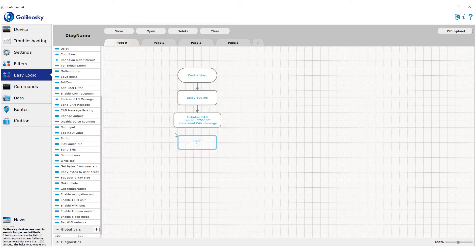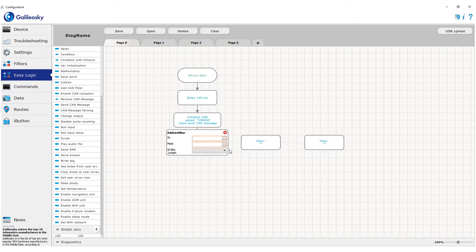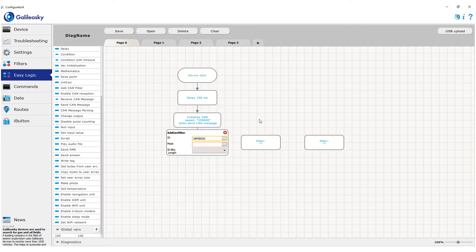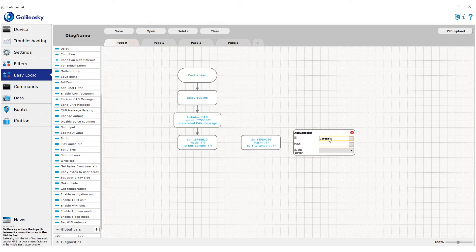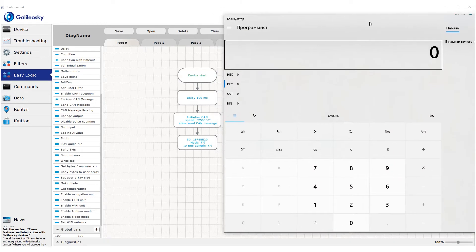Then we start adding CAN filters to the scheme. Filters are needed to work only with the identifiers we need and ignore all the rest. Each identifier uses a separate filter block. In the first field, we enter the ID of the message. As I already said, EasyLogic works with decimal values only, which is why we can remember one of the previous lessons and make the reading of the algorithm more convenient. We can create variables with names as hexadecimal identifiers and record corresponding decimal values into them.